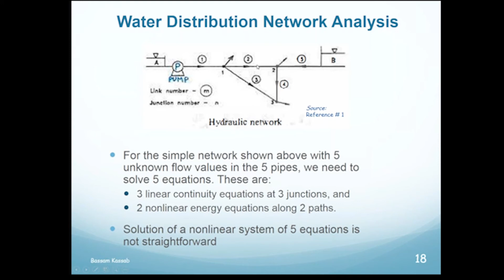So you get that pump curve, but how does it help you? You need to understand your system. By system, it could be the whole water distribution network, or it could be a simple system like I showed you earlier - if you have, say, 2 reservoirs and a pump between them and 3 pipes. So when you write that energy equation from point A to point B, that's an equation describing your system. And that's when you bring it here and plot it - plot the head of the pump versus the flow.